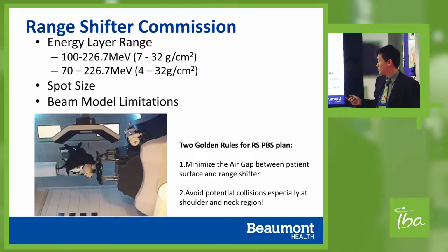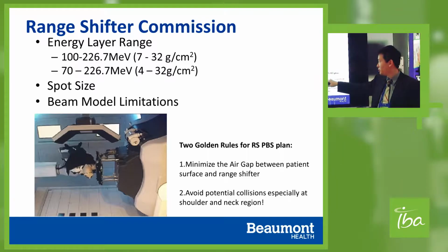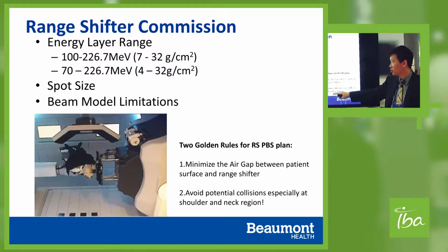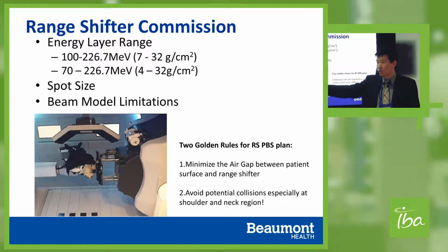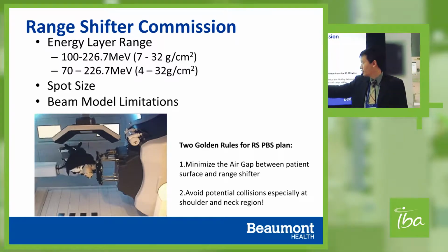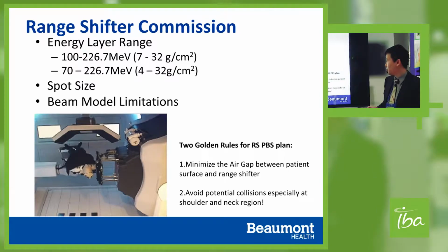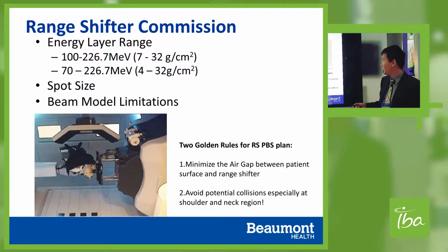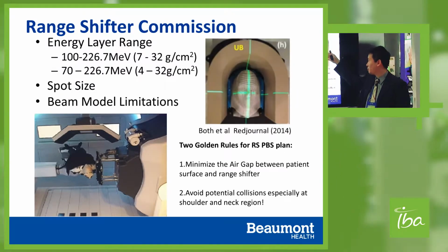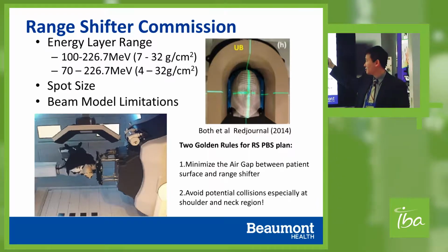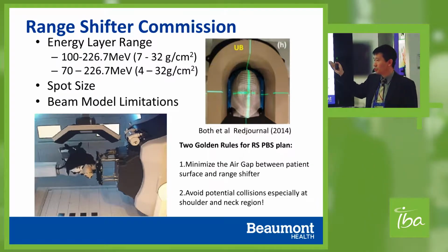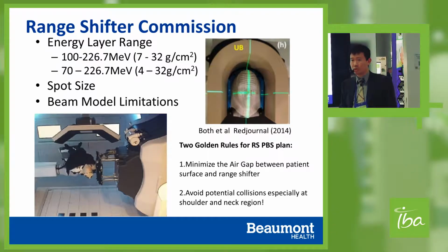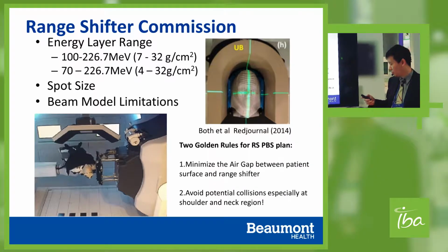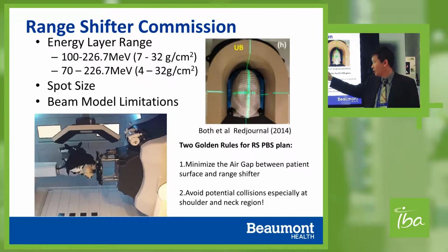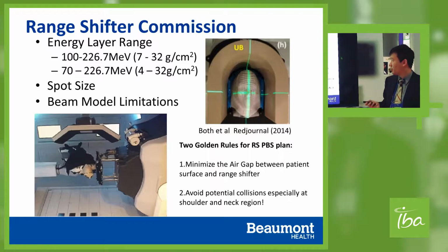But there are two golden standard rules for range shifter commissioning. You want to minimize your air gap and also avoid potential collisions when you use this setup. When you rotate the gantry, you might potentially hit the patients due to the clearance issue. At Pennsylvania, what we did is build the U-bolus around the patient body, so it was consistent and minimized the air gap. However, introducing extra hardware into the proton workflow is really difficult and also time-consuming. But now more and more people are drifting into this continuous range shifter model for the Proteus One system.